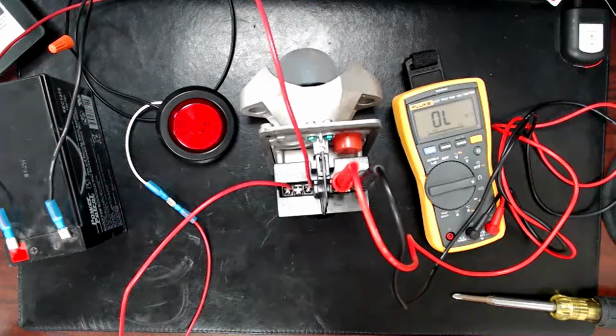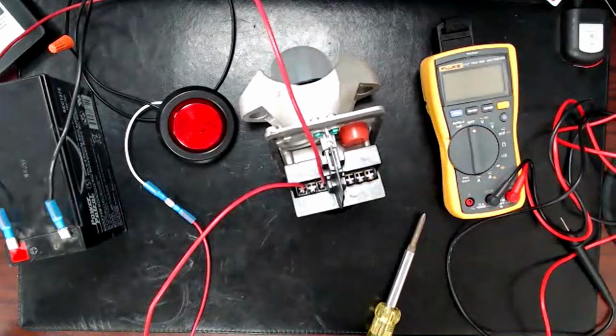Hey, the 24 volts you were saying for the IFP, the 24 volts coming off of the panel, we're using it for the dialer, and as well we're using it for the 24 volts for the bell. Do you hook them up at the panel in series or parallel? I would say parallel, just so that if anything happens or you got a bad wire nut or a loose connection, you don't lose your dialer.